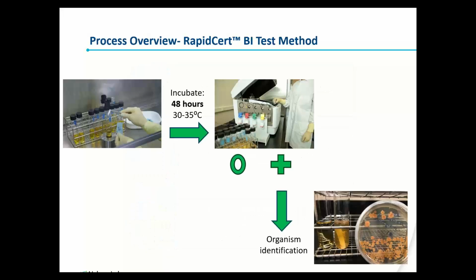Okay, so here's the process overview for the RapidCert BI test method. So you can see it has a very similar flow to that traditional test method. We would take the biological indicator, remove it from its container, still test it in a soy-based media. That would be for a 48-hour minimum time frame rather than that 7 days, and it's still at 30 to 35 C. From there, rather than doing a visual inspection of the containers to look for turbidity, we would remove an aliquot from these test containers and run that through this test system, which allows for the introduction of reagents to detect the presence of ATP, and that is reported out in relative light units.